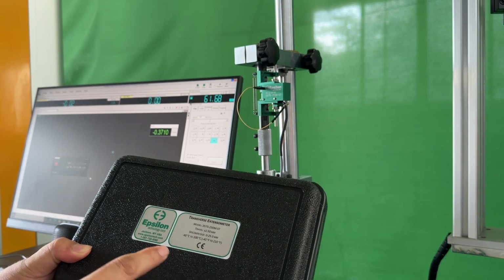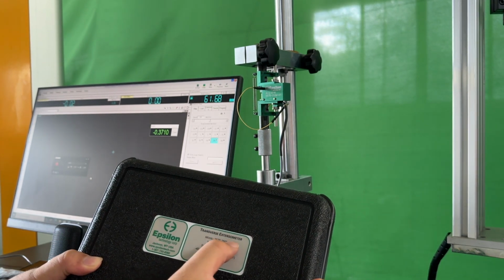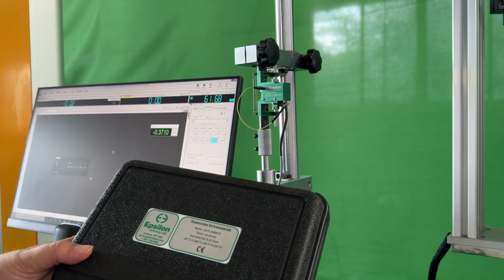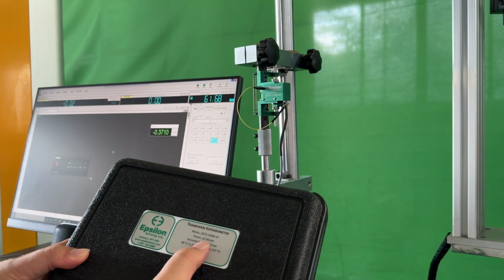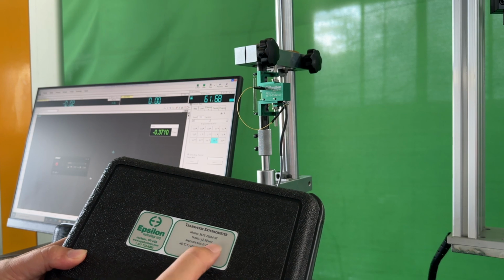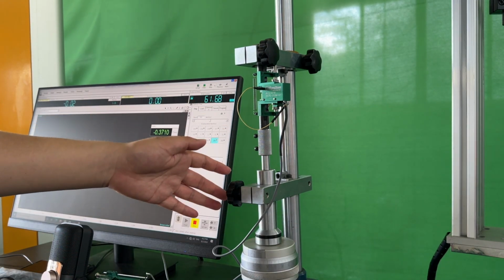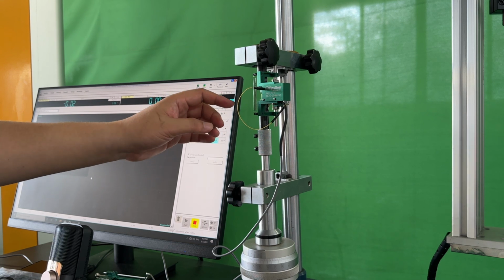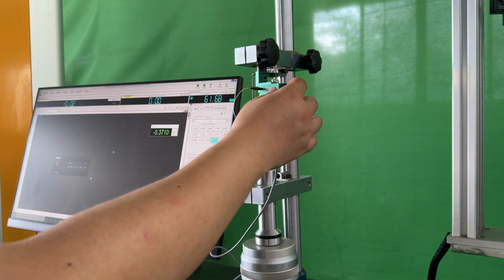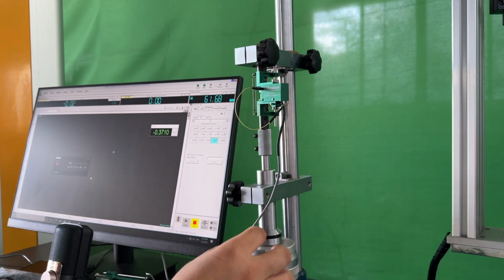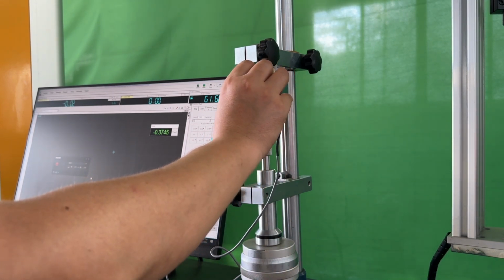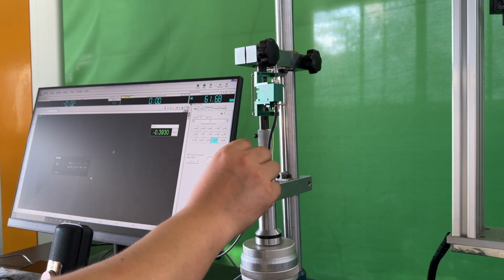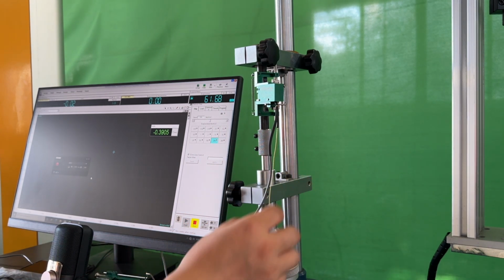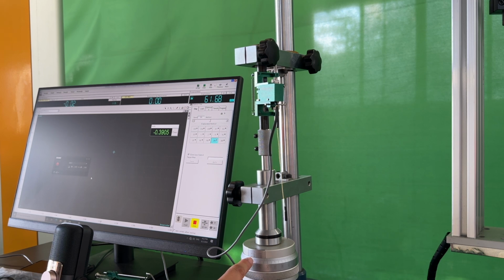Here are the steps for calibrating the transverse extensometer. The gauge length is 25 millimeters, and the travel is 12.5 millimeters. This is a standard extensometer calibrator. First, we will clamp the extensometer onto the calibrator and loosen the pin. Then we will adjust the device to either 5 millimeters or 10 millimeters. At a later time, we will begin the calibration from 0 millimeters.